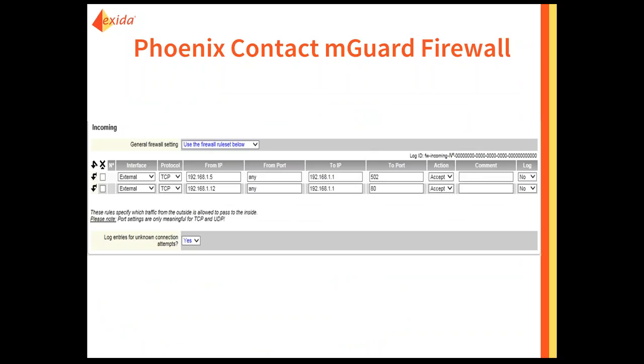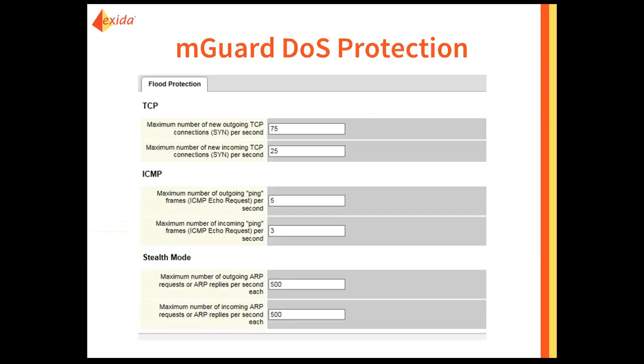Phoenix Contact M-Guard has a web-based interface similar to the Moxa, with rule sets and denial-of-service protection. With these end devices it is extremely important to limit the amount of traffic that reaches them. We can emulate the failure by simply creating a broadcast storm, causing a PLC to fail, corrupt, and flash its outputs on and off. In a real industrial system, that could be catastrophic.